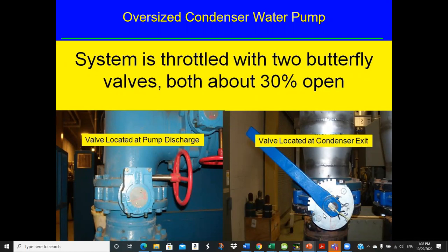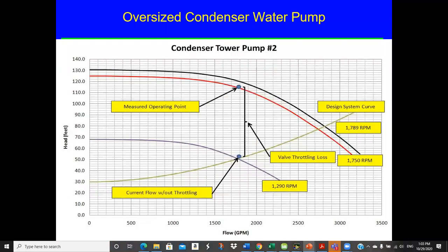So then this is on the same line. This is at the chiller, and then they pinch this one. So this and this are both throttling the same pump. That poor little pump was throttled way back. And so that's the analysis of it.